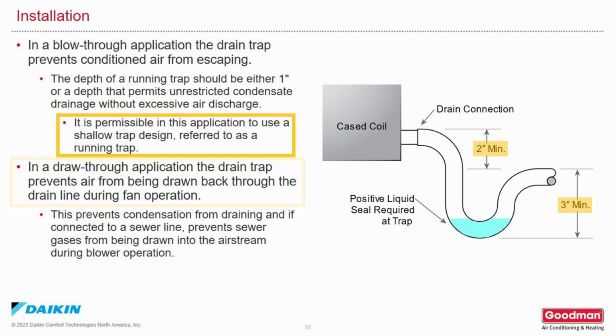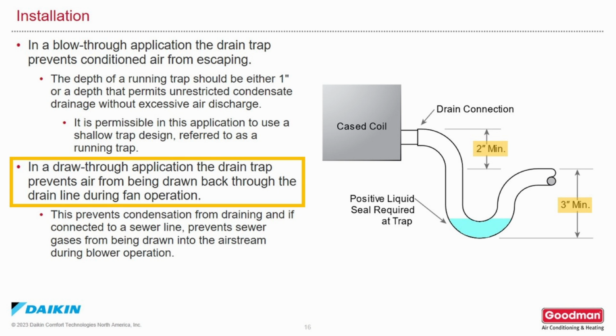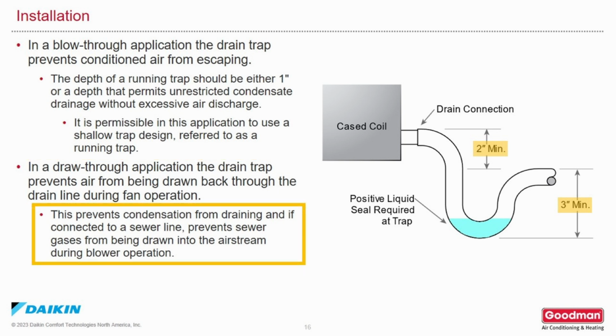In a draw-through application, the drain trap prevents air from being drawn back through the drain line during fan operation. This would prevent condensation from draining, and if you're connected to a sewer line, it prevents sewer gases from being drawn into the airstream during blower operation.